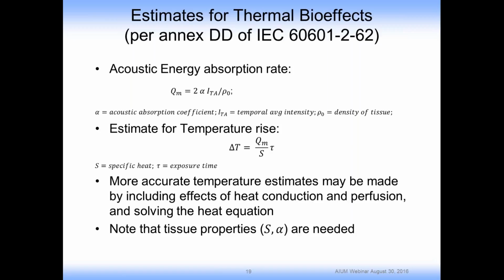Basically, you have the intensity represented by the ITA at some position. If you know the acoustic absorption coefficient for the material, then you can calculate the energy deposition that the wave deposits as it propagates through the tissue. And that then becomes a heat source. Aficionados of heat conduction know that technically that should be used in a full solution of the heat equation, but in many cases that can be approximated if you can neglect perfusion and conduction. If you have the heat source and the specific heat of the tissue, the temperature rise is given by this simple equation where tau is the exposure time.